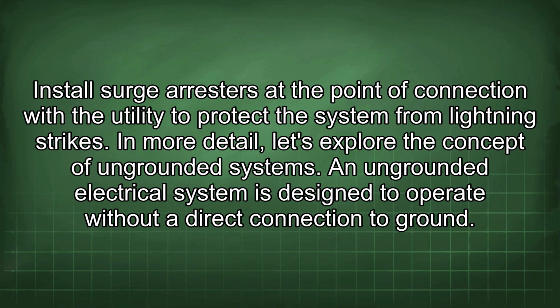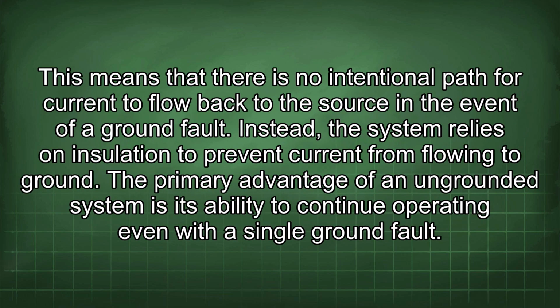In more detail, let's explore the concept of ungrounded systems. An ungrounded electrical system is designed to operate without a direct connection to ground. This means that there is no intentional path for current to flow back to the source in the event of a ground fault. Instead, the system relies on insulation to prevent current from flowing to ground. The primary advantage of an ungrounded system is its ability to continue operating even with a single ground fault.